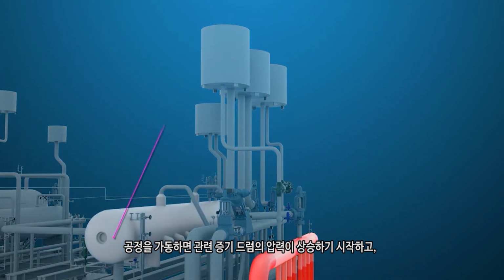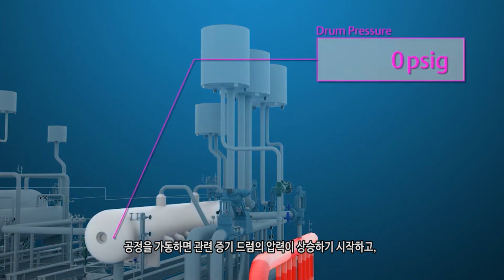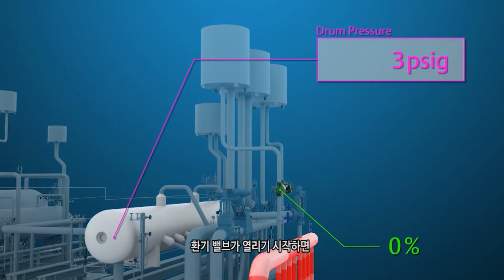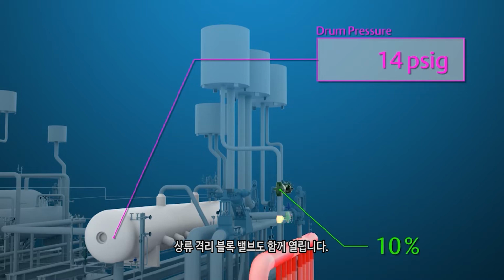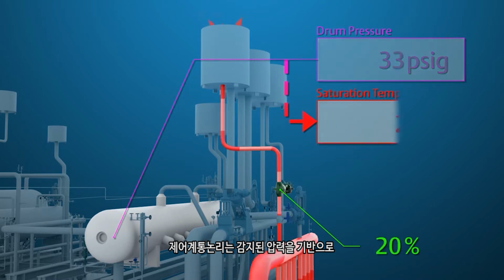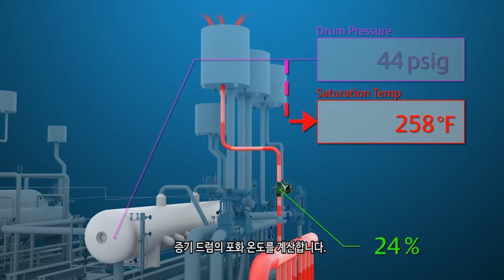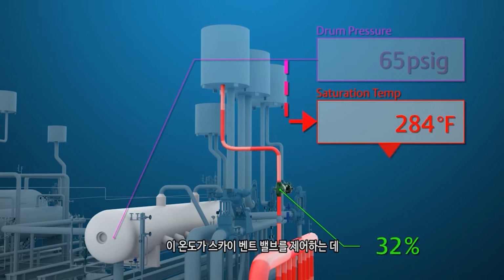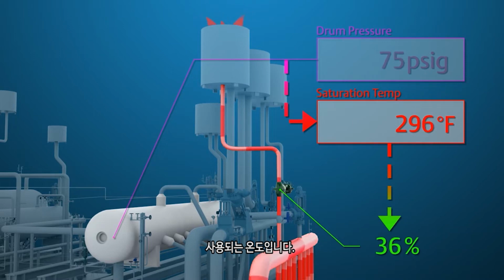At startup, when pressure in the associated steam drum starts to build and the vent valve starts to open, the upstream isolation block valve will open. The control system logic will calculate the saturation temperature of the steam drum based on the sensed pressure. This is the temperature that is used to control the sky vent valve.